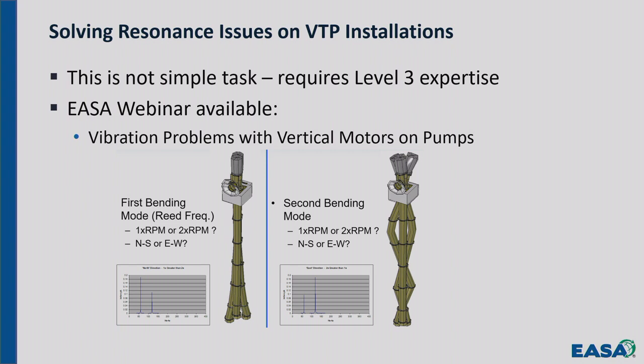There's six standard vibration modes. If you ask them those questions and they know those answers, they do a pretty good job of it. If they say, what's a mode? That's not the person to be trying to solve a structural resonance problem. Okay? So we already talked about that. First and second bending modes in the pump and in the motor, in line with the discharge versus perpendicular to the discharge, and then put it on a VFD.